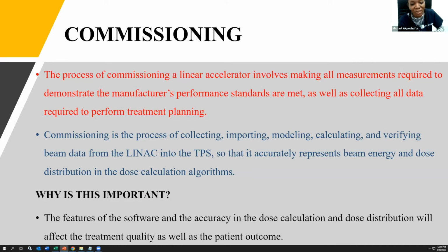Then you import this data into the TPS. You process it to ensure that the dose calculation algorithm can accurately represent your beam energy and you have proper, accurate dose distribution within your target. Now, this is also very important because any error made during this commissioning process will affect every treatment, all through the lifetime of that machine. So that is one important reason why there is no room for error during commissioning, because any error at that point will affect the quality of your treatment outcome.